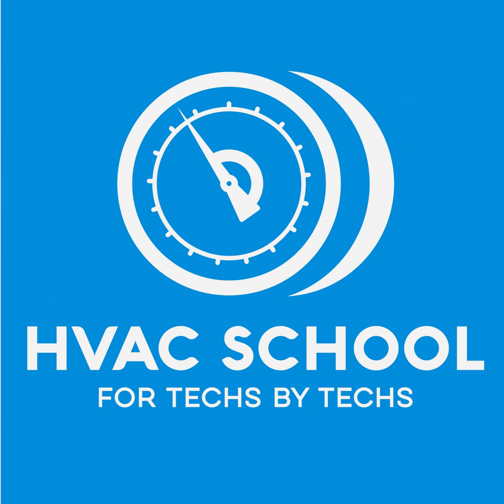One of my pet peeves is people talking about SEER ratings all the time. SEER rating, SEER rating. From what I understand, a SEER rating is how efficient it is at 100% cooling capacity, correct? For the most part. Yeah. So, SEER is a funny topic because EER is so simple. EER is always at a given point. At any point in time, you can tell exactly what the EER of a piece of equipment is. We're just dealing with capacity and wattage.